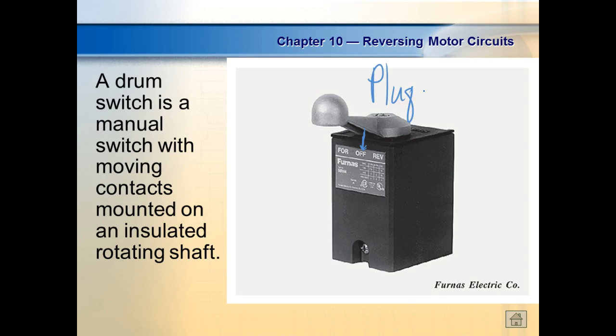So instead of adding a real fancy circuit, we have an anti-plugging switch. It's a centrifugal switch that spins with the motor, and the motor can spin in either direction. What it would do is open up the other lead, kind of like the electric seal-in. This would also add a feature to that, if I can find it.